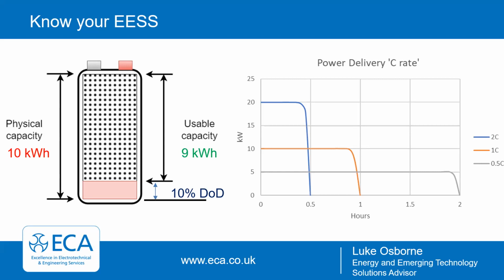On the right-hand side you can see the power delivery, the C rate. So even though someone has a 10 kilowatt hour battery, it doesn't always mean they can draw 10 kilowatts of power from that. This is normally represented in a capacity rate, a C rate. So in this example, if you had a 10 kilowatt hour battery - we'll look at the orange line here - at a C rate of 1, this is able to deliver 10 kilowatts of power for 1 hour. But if it's designated at a C rate of 2, that's its maximum continuous power that can be delivered.